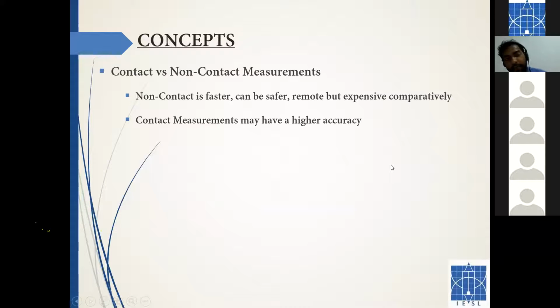Going on to some concepts. Why do we need contact and non-contact measurement? As you know, infrared thermal imaging is a non-contact technology. We don't have to touch the surface to get the measurement out of it, right? But on the contrary, other devices like resistive thermal RTDs, thermocouples and thermistors and other instruments always have to touch the surface, right? So they are contact forms of measurement. But infrared thermal imaging is the only way we can get non-contact measurements out of a material.